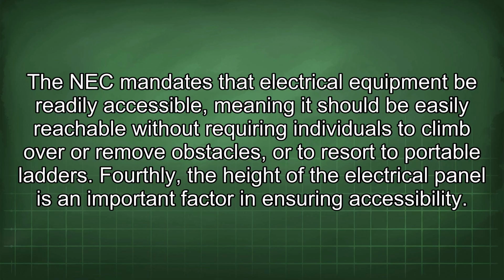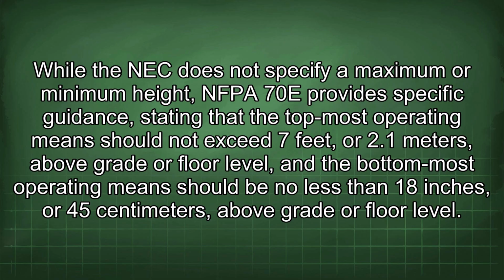Fourthly, the height of the electrical panel is an important factor in ensuring accessibility. While the NEC does not specify a maximum or minimum height, NFPA 70E provides specific guidance stating that the topmost operating means should not exceed 7 feet or 2.1 meters above grade or floor level, and the bottommost operating means should be no less than 18 inches or 45 centimeters above grade or floor level.